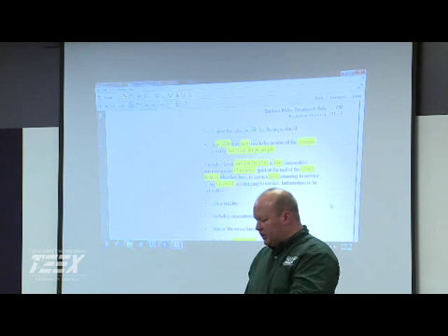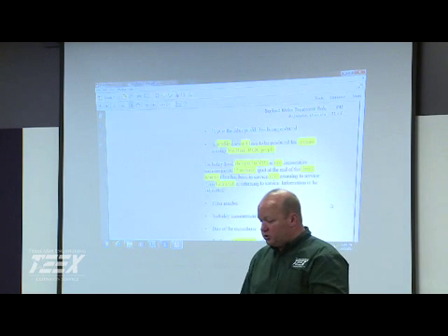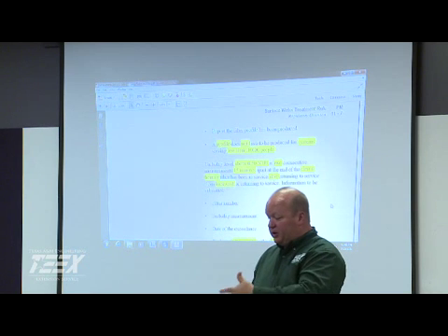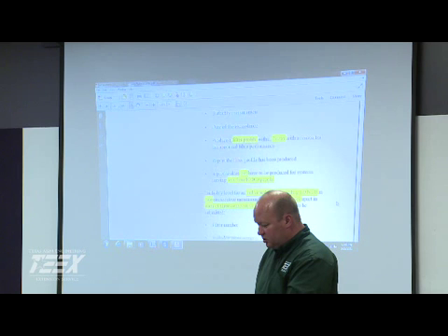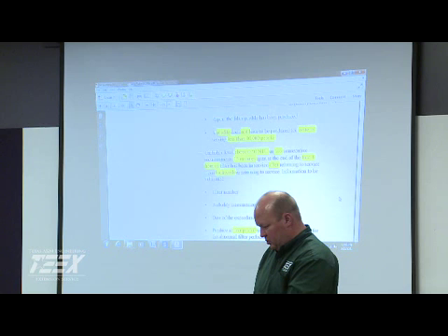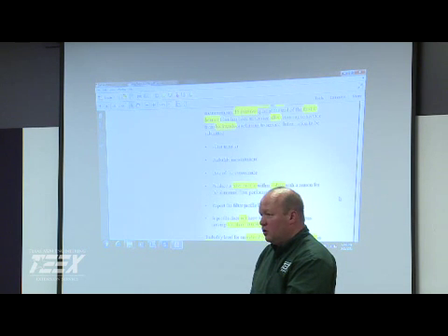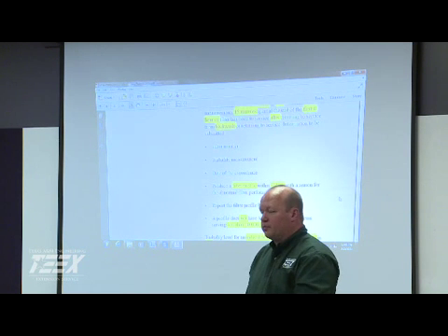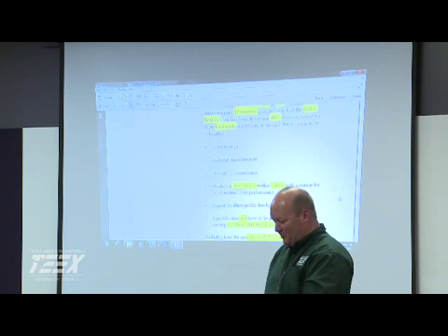Talking about systems less than 10,000, they won't have to do the profile, so that figures into some of y'all's also. If you have your turbidity, and here's your 0.5, y'all are requiring that as a more stringent component of it. On our filter performance report, it starts out at 0.5 as the first question: did you have any readings above 0.5 in 2 consecutive readings? And then it goes up from there. Did you have anything at 1 and 2? I didn't read ahead, but I didn't see that, so no problem.